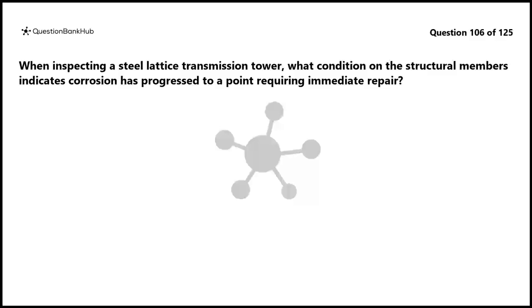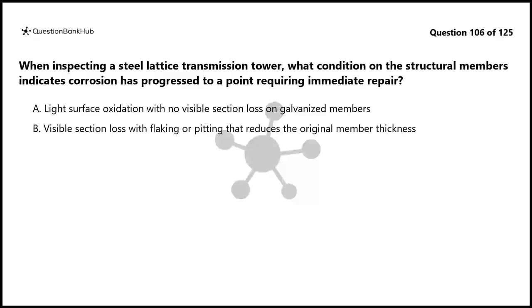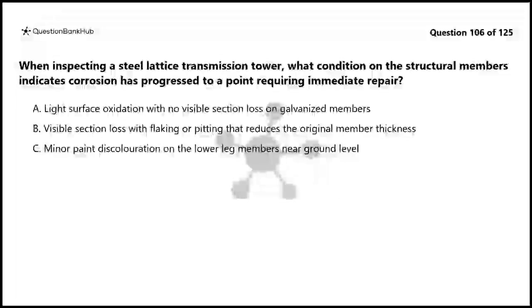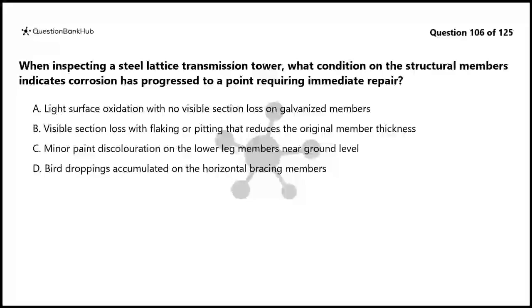Question 106. When inspecting a steel lattice transmission tower, what condition on the structural members indicates corrosion has progressed to a point requiring immediate repair? A. Light surface oxidation with no visible section loss on galvanized members. B. Visible section loss with flaking or pitting that reduces the original member thickness. C. Minor paint discoloration on the lower leg members near ground level. D. Bird droppings accumulated on the horizontal bracing members.